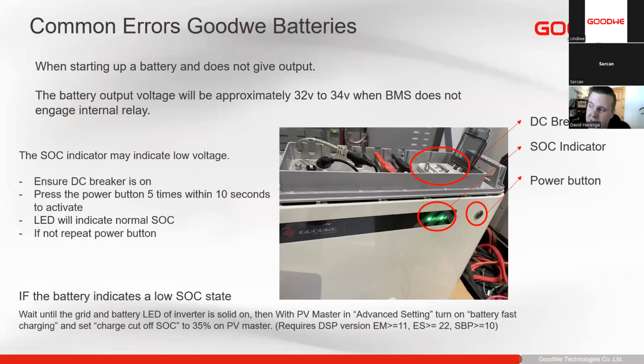So if we're installing this from an older inverter, we'll just have to make sure that our firmware versions are correct, on the correct versions, to enable us to use this feature. And that way we'll know our batteries are correctly charged, especially if we need to store the batteries for longer. I know in some countries you might have to install, and we wait for utility to come to the site before we can fully switch on and commission the system. So just make sure to charge those batteries up, and then we can switch the system off and leave it till the utility company comes to have a look at it.